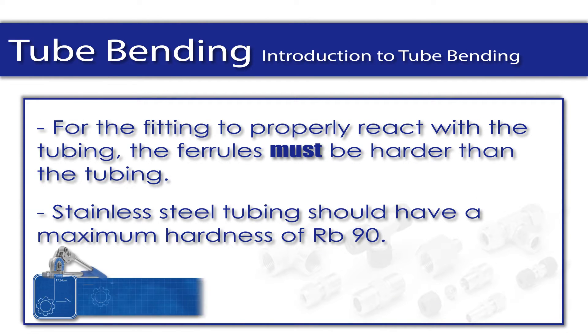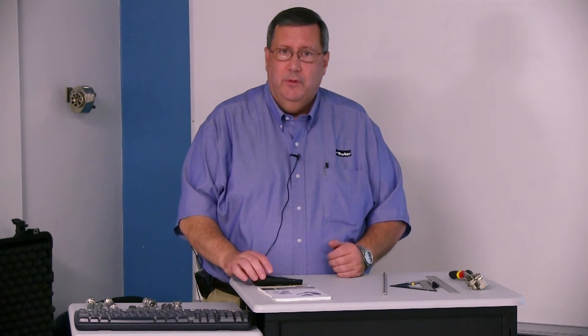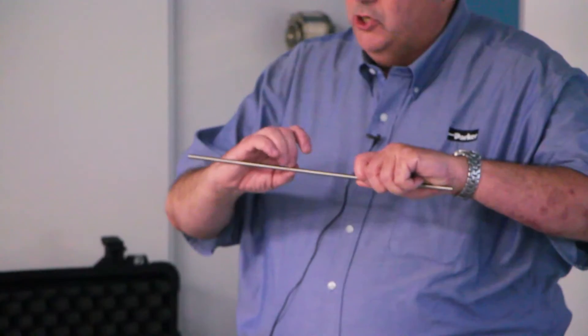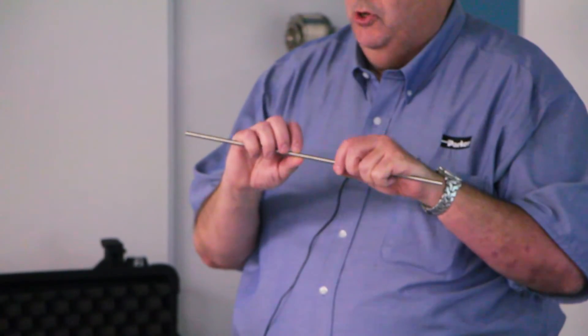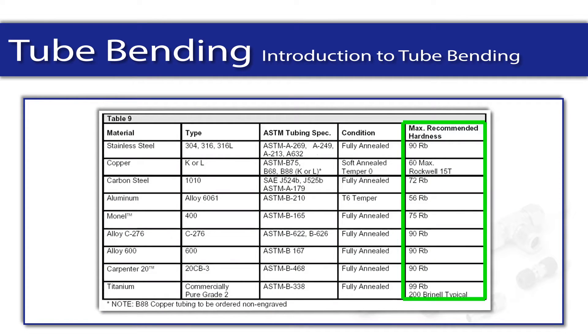The next thing we want to talk about is tubing hardness. For the fitting to work, the tubing must react with the ferrules. The ferrule must be harder than the tubing. We spoke about that already. You just can't use any tubing. We'll talk in the next couple slides about the type of tubing you use for instrumentation. There are special grades where the tubing is actually annealed, meaning there's a heat treatment process that makes it soft, so not only can the ferrule grip onto the tubing, but so you can actually easily bend the tubing.